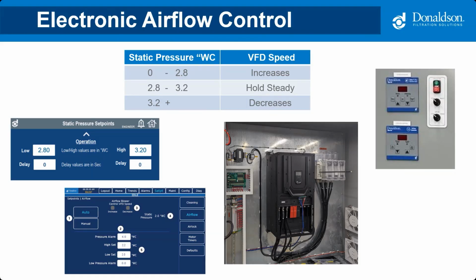And to maintain the ideal airflow, we are using a target range of the static pressure to increase, decrease, or hold the speed steady. Depending on the tap location, that is going to change how this table behaves. The static pressure, at the low end, could be decreasing the speed of the VFD or increasing it, depending on how everything is set up. So I don't want you to think that this table is always how every system is set up. It really depends on that tap location and the pressure on the equipment.